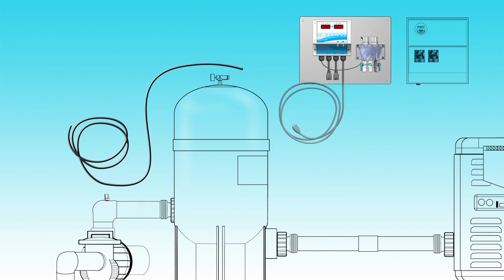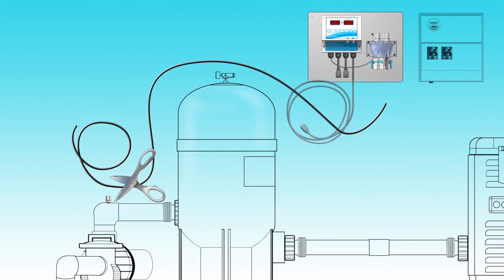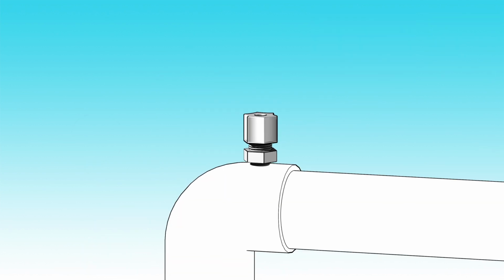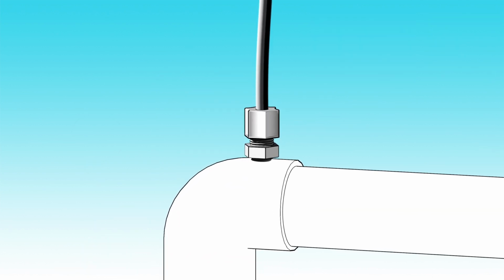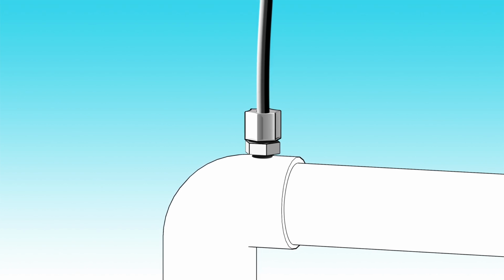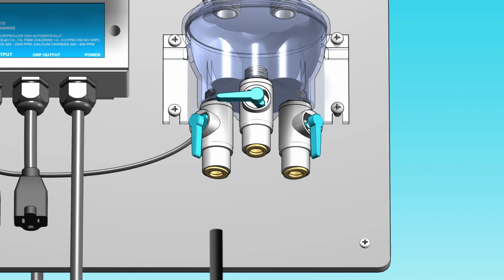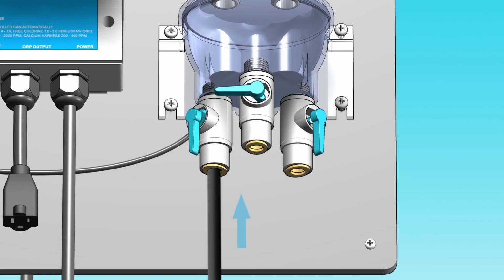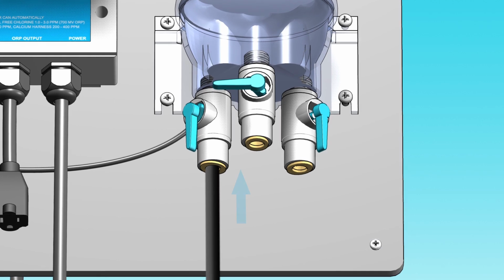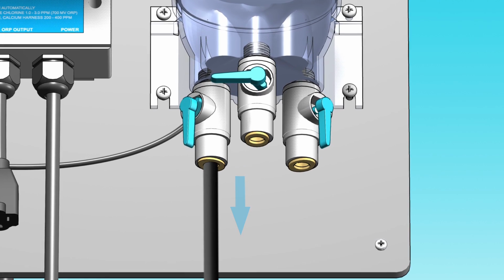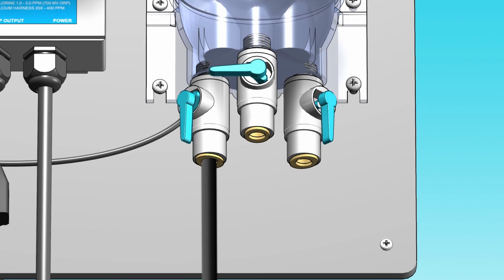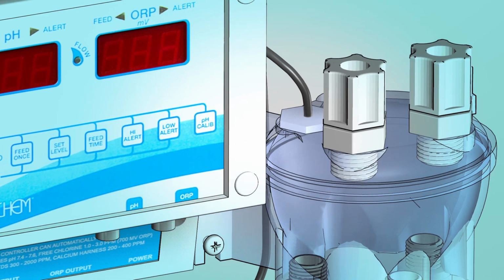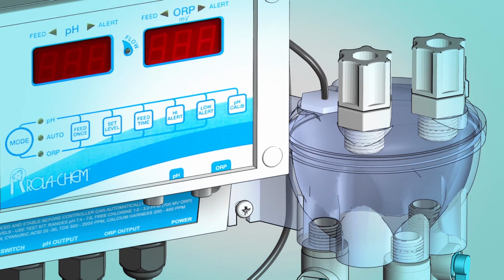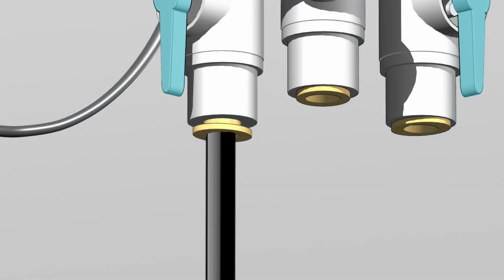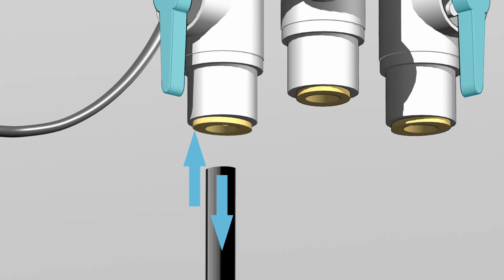Measure a length of tubing long enough to allow easy routing from the pipe fitting to the flow cell. Insert one end of the tubing into the compression fitting and hand tighten the nut to secure the tubing. Insert the other end of the tubing into the valve on the far left of the flow cell. Push the tubing into the valve as far as possible and pull back slightly. This will lock the tubing in place. This port contains an integrated flow switch that will prevent chemicals from feeding into the system when the system is off. To remove the tubing from the valve, push the retainer inwards while pulling the tubing away from the valve.